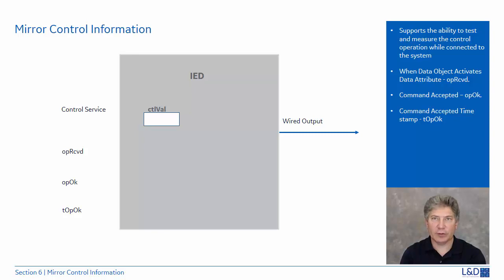The feature of mirroring of control information was added to IEC 61850 Edition 2. This supports the possibility to test and measure the performance of a control operation while the device is connected to the system.